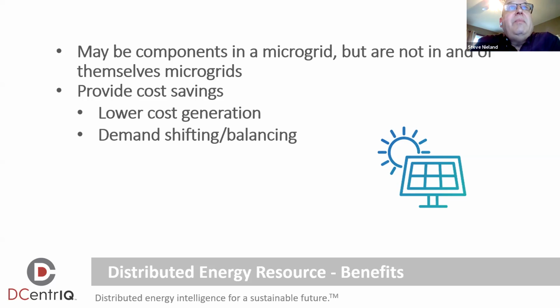By putting a storage system on site, I can shift where that demand goes. For example, I can install solar plus a battery, charge the battery during the day and discharge at night. Or if I get a favorable electric rate at night, I can just use a battery system: charge it at night during the low rate, discharge during the day at the higher rate, and cut my demand down.